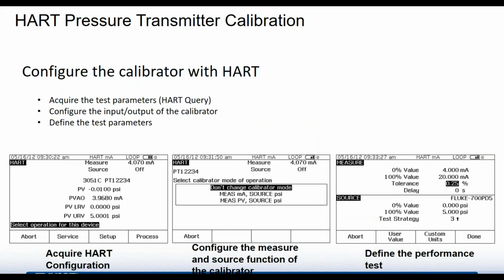So the next thing you want to do is connect HART communication to your transmitter. In this case, we've taken our calibrator and connected it up, and you'll see you're going to get things like your tag ID name, your PV values, your upper and lower range. This information is automatically available through HART. So once you connect up, that information is available instantly for you.